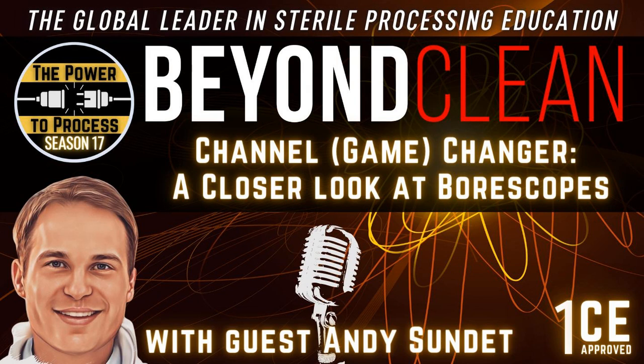That's awesome. So we kind of hit why and where and when. I guess the other "when" question is, is it every device every time? Is it an audit tool? We see groups that are implementing borescopes handle it multiple ways. Sometimes they start with every device every time and get some feedback that that's too much, so they use it as an audit tool and take a certain number of devices at a certain frequency and go through them with the borescope. Then from there, they develop a plan. I think those are all good solutions, but things to think about.